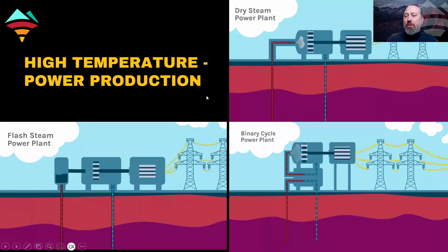In the lower right is a binary cycle power plant. In a binary cycle power plant, you don't actually use the fluids directly. You have two separate loops: one pulling up the hot fluids from underground and re-injecting them, and parallel to that at the surface, another loop of a working fluid that vaporizes at a significantly lower temperature than water. The fluids from underground never actually touch the turbine. Instead, it's that working fluid that vaporizes and flashes to power the turbine.